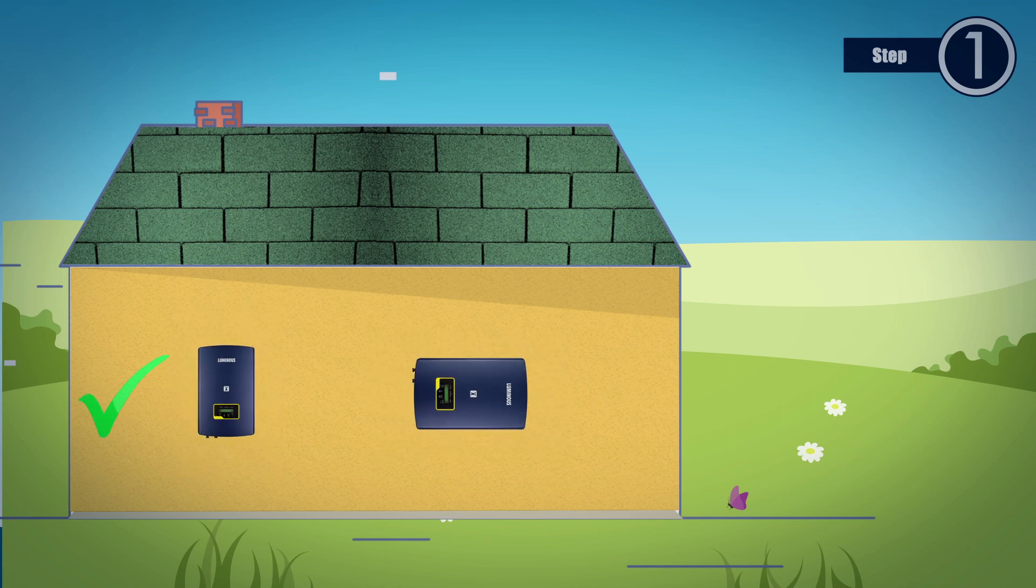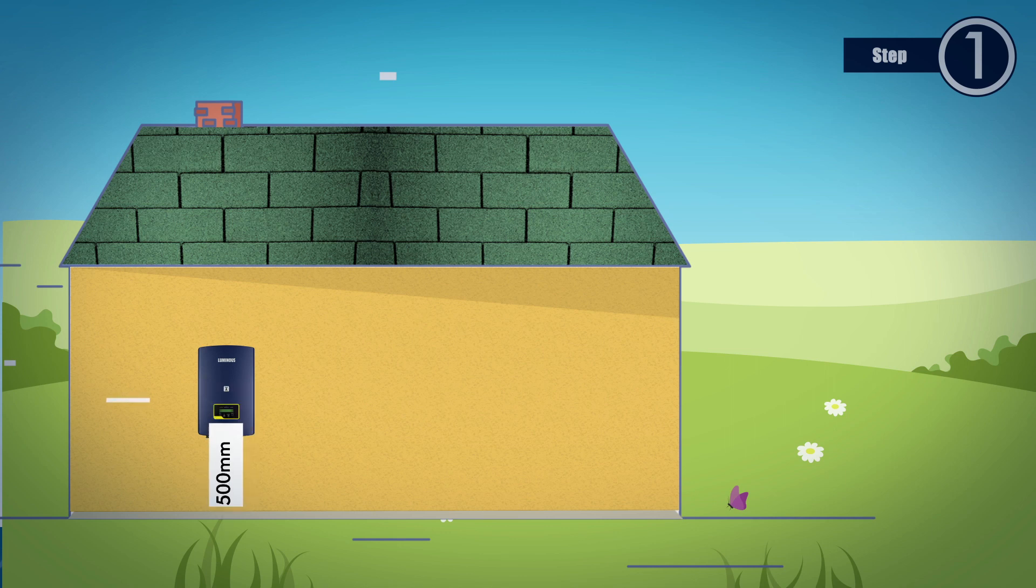Inverters should be mounted in a vertical position, having a minimum of 500 mm clearance distance from the ground, ceiling and the side walls.